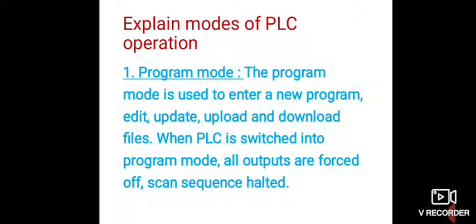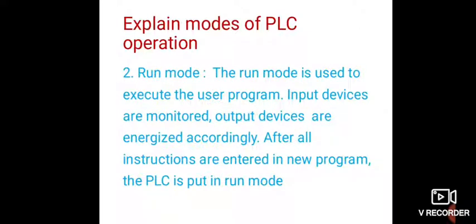The program mode is used in the PLC. When the PLC is in program mode, all the outputs are off and the scan sequence is halted. All the outputs are off means the PLC is not actuating any output, and it is not scanning any input. Both input and output are halted because we are writing the program or editing the program.